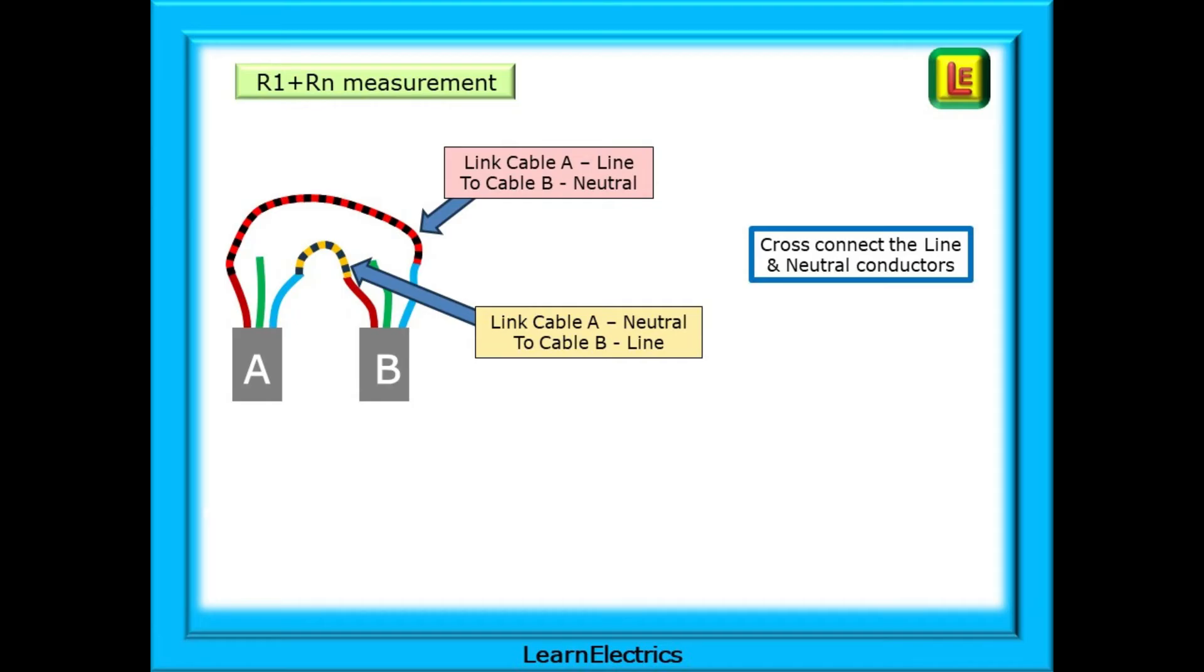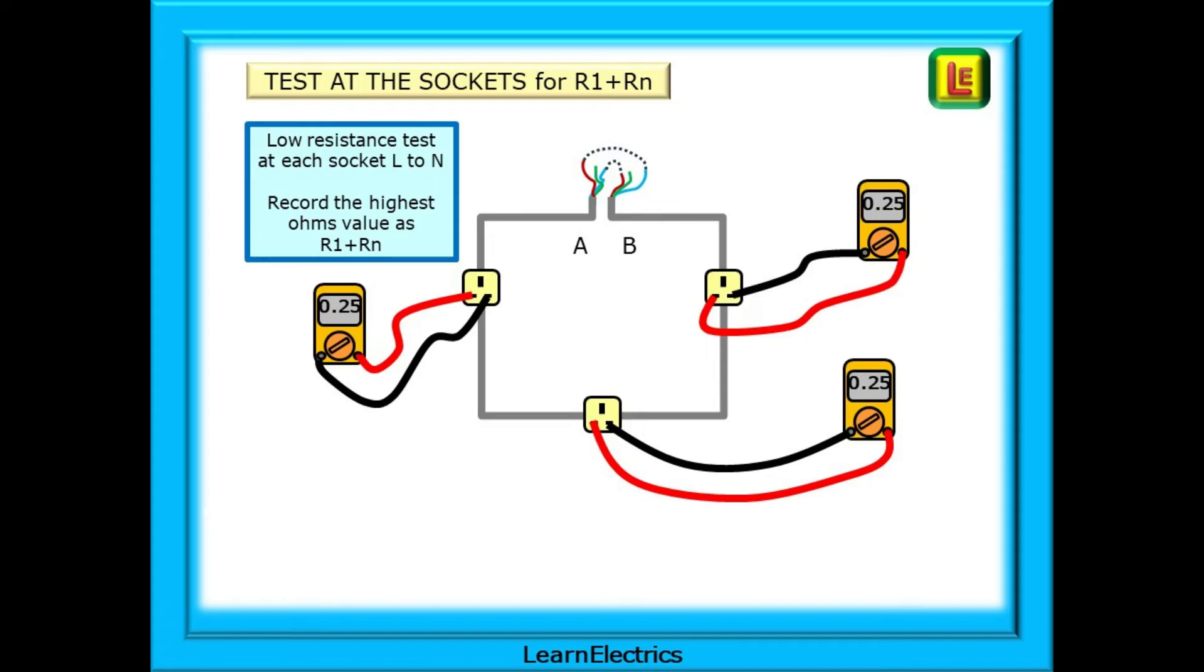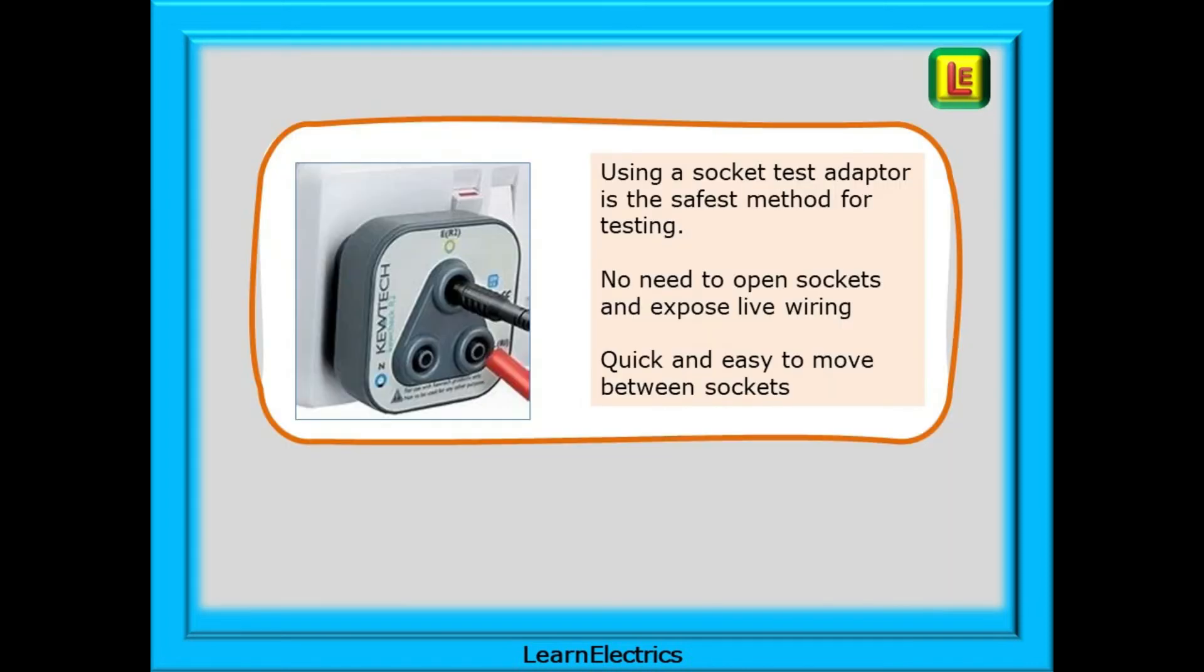Now forget about the consumer unit and go to the sockets. Carry out a low resistance ohms test at each socket between line and neutral. Record as you go and use the highest value in ohms as you test each socket. If your meter has a test lead with a 3 pin plug on the end, it won't do this test without you repositioning the jack plugs in the back of the test meter for each test. Far better, I think, to use the leads with a 4mm jack plug on each end and a socket test adapter. Using a socket test adapter is the safest method for testing. No need to open sockets and expose live wiring and it's quick and easy to move between sockets.